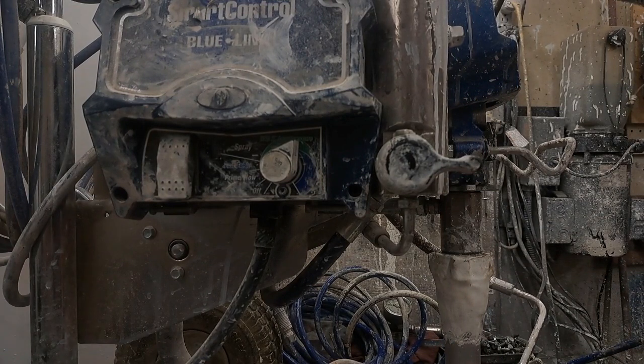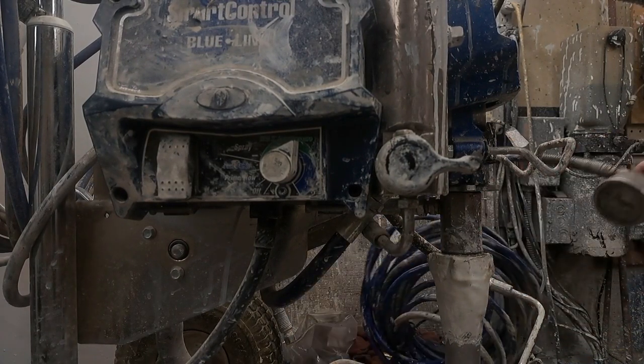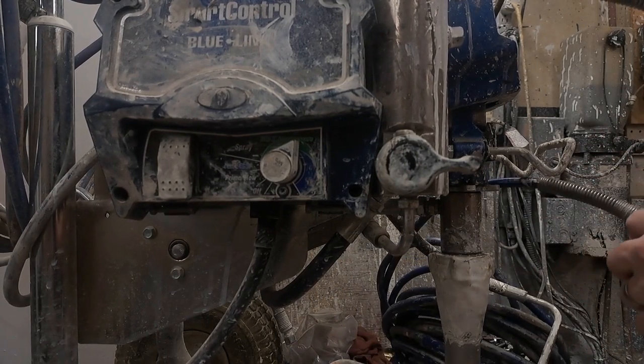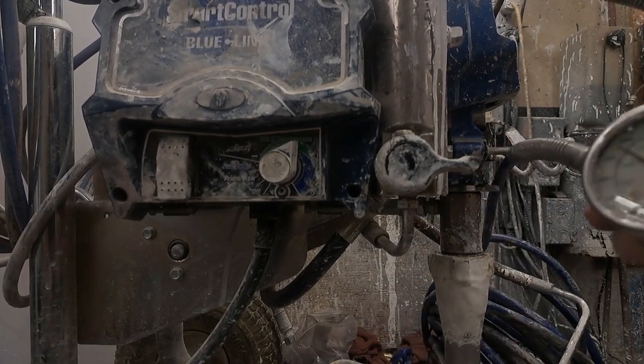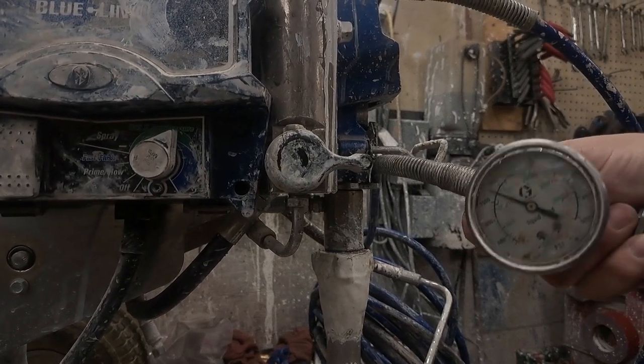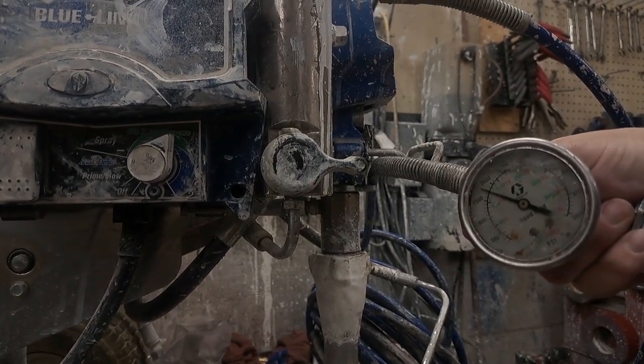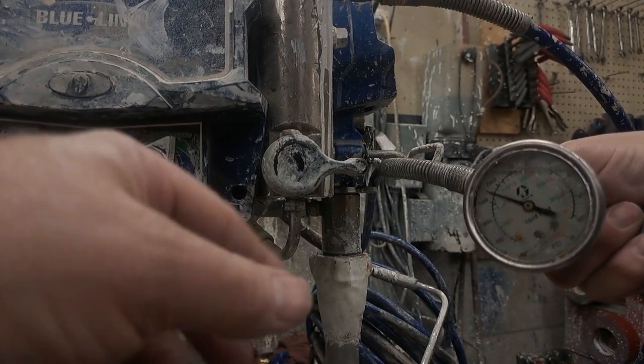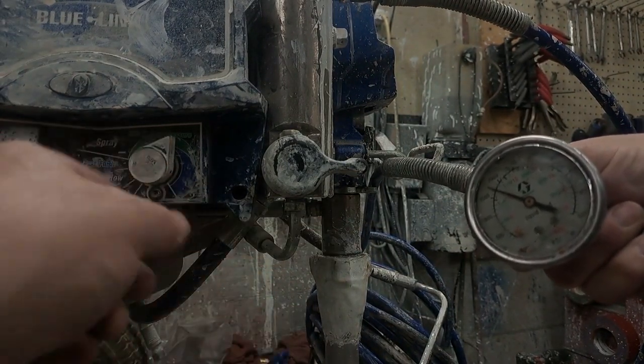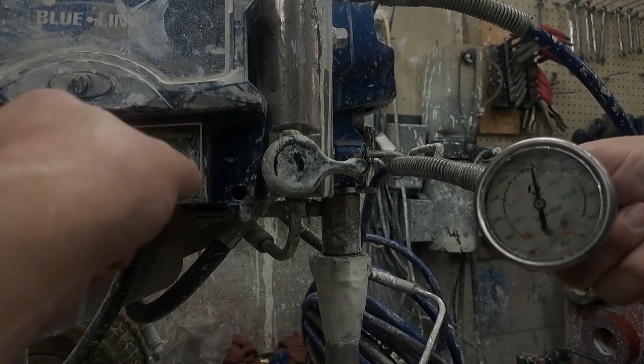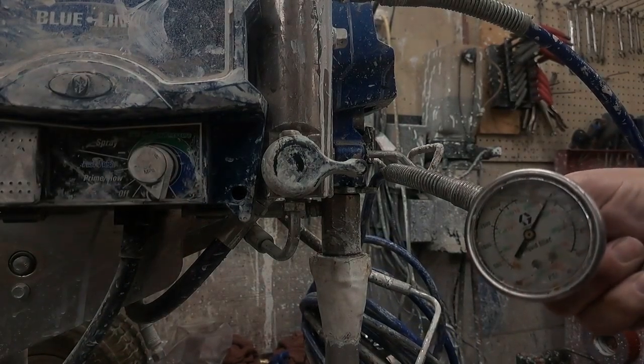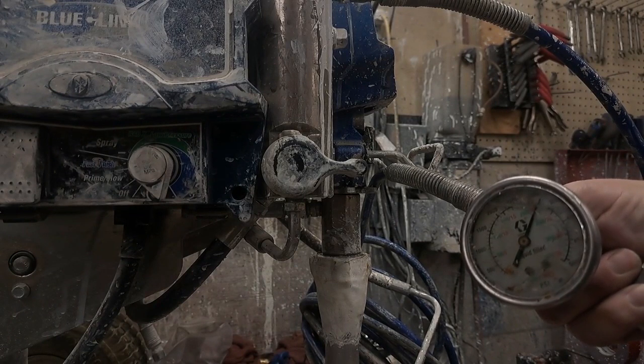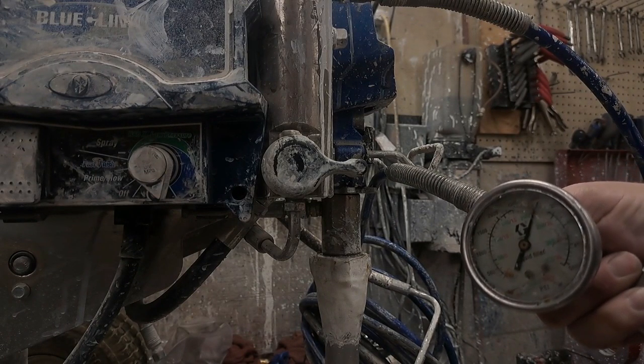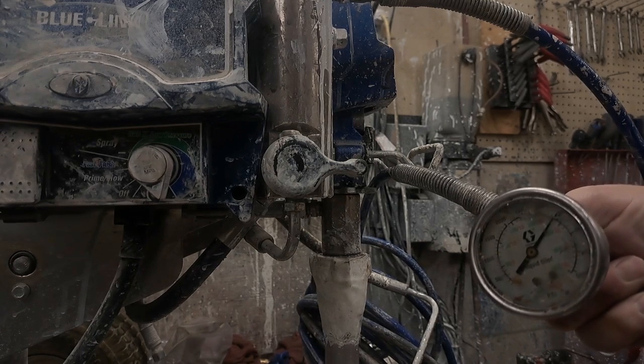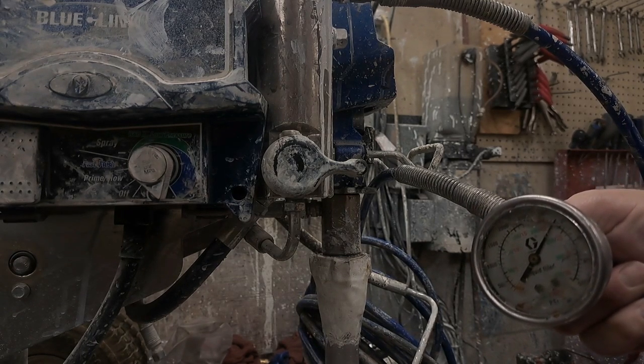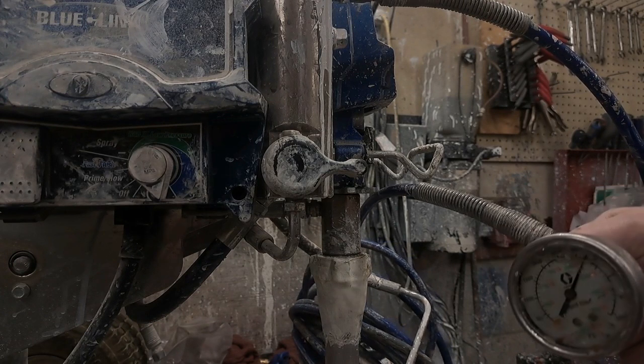Alright, so we built pressure and it stopped, which means we don't have a pressure leak anywhere. I'm going to show you the gauge - this is my gauge, I don't trust the computers. If something's off in here, you won't know it because the computer's telling you different. So we're sitting here at just above 15. We're going to kick it all the way up. So we're sitting at 3,300 psi - it'll probably stroke again. We've got air inside of the line, so the air compresses and changes the calibration of what's going on inside. So everything's good.